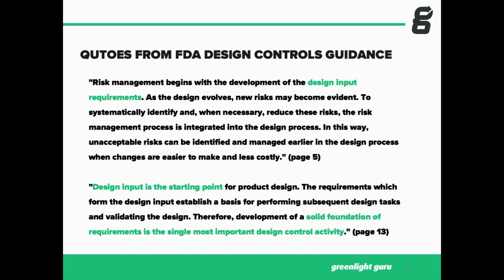You can see it talks about the idea that risk management begins with the development of design input. So there's this relationship between risk and the design control process. These things are really very much joined at the hip. They're very much connected together. So use one to help you with the other, and it will make your product safer, more effective, and mitigate risk throughout the entire process.